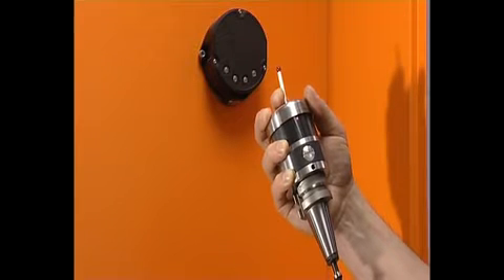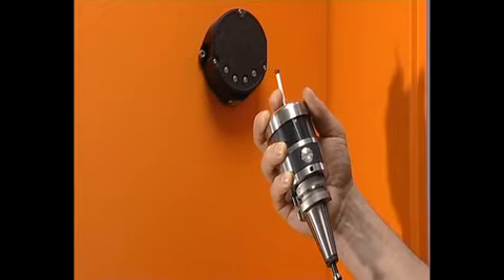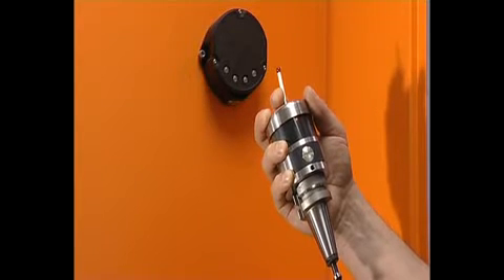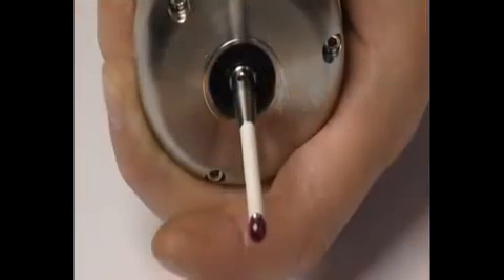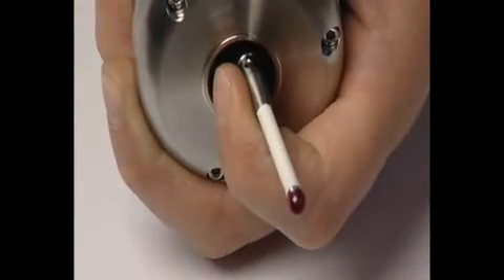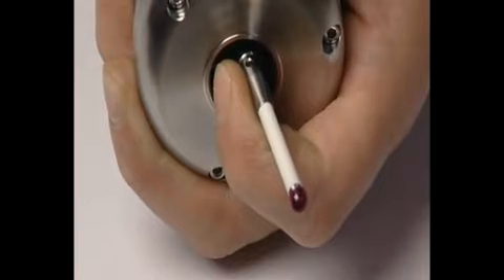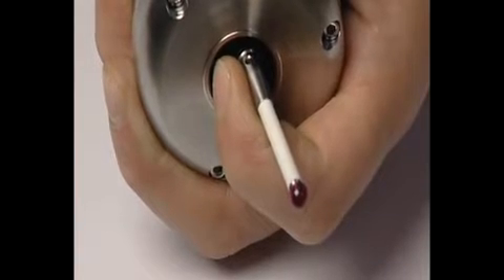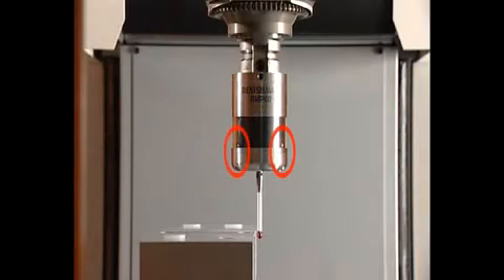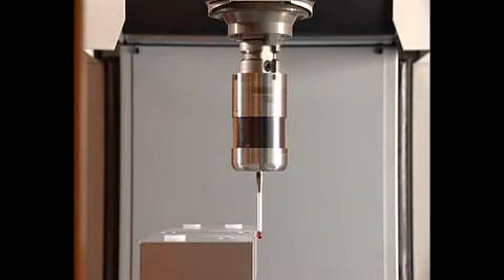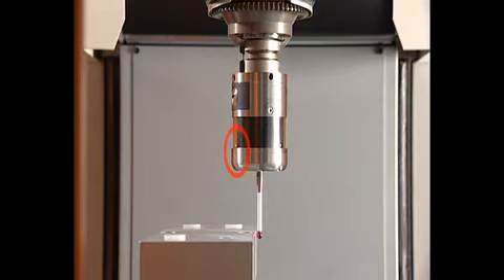The RMP60 spindle probe is multifunctional. All settings are configured using the trigger logic technique. This allows you to review the probe settings by observing the multicolor LED display. For ease of use, the RMP60 has 3 LEDs spaced evenly around the body of the probe. Each one does exactly the same thing. When observing trigger logic, you need only refer to one of them.